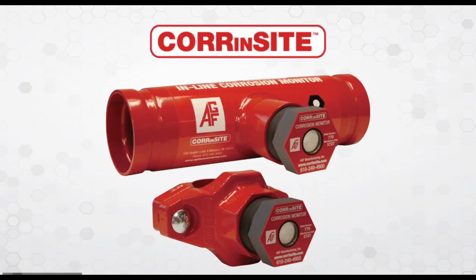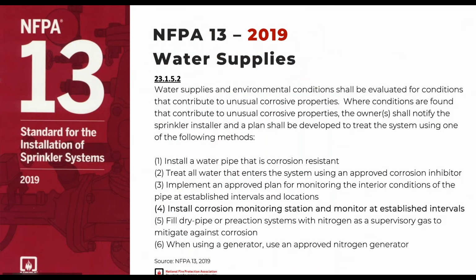Moving on to how do I tell if I have a corrosion problem? So the air vents help us stop having corrosion, but if you've had any type of corrosion related event and pipe failure, it was recommended to us that we create a device that would tell people they're about to have a corrosion problem before the actual water damage event. So NFPA 13 has gotten much more detailed, and the chapters associated with the quality of how the water is both supplied to a system and maintained in a system have increased each year.